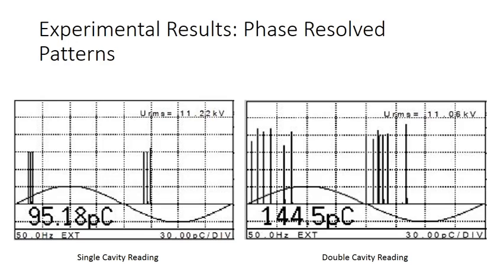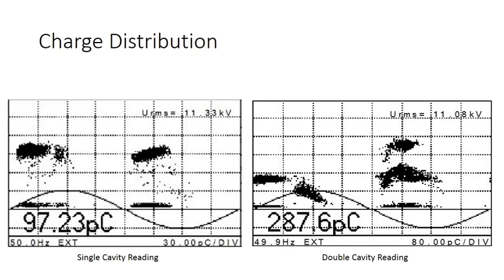The double cavities had a high charge pulse rate over a wider space and bigger charge magnitude. There is a clear pattern distinction for single versus double cavities, as they also differ in charge cloud clusters and the magnitude they occur at. Therefore, cavities in close proximity to each other degrade the insulation much faster.